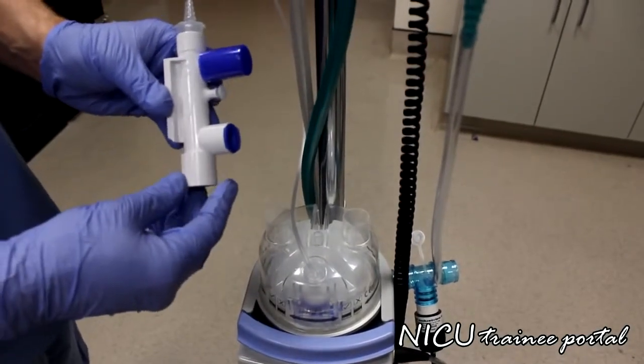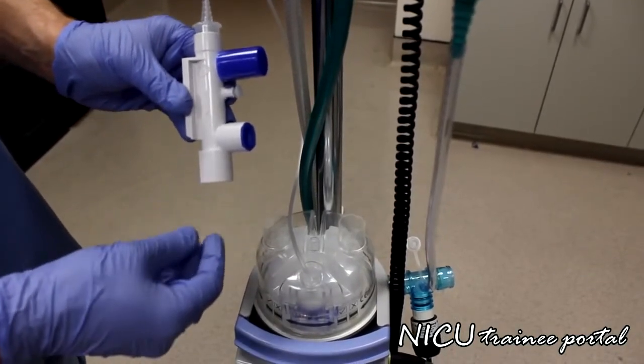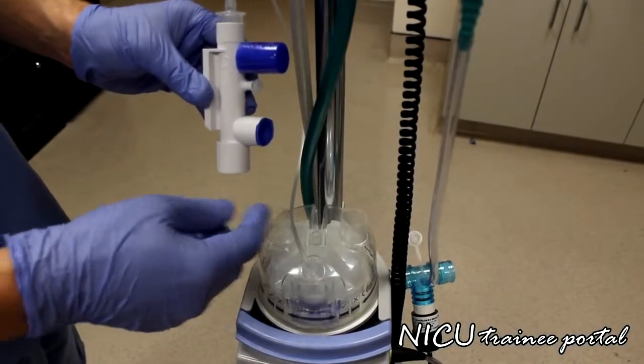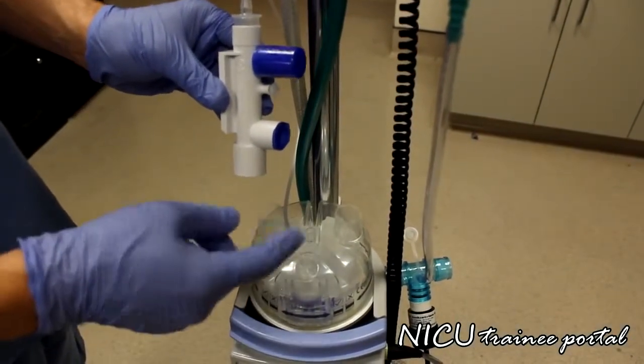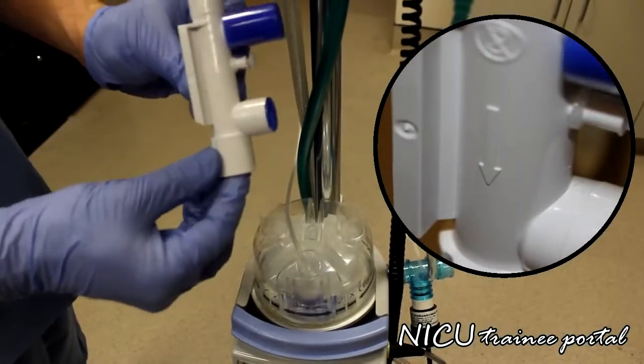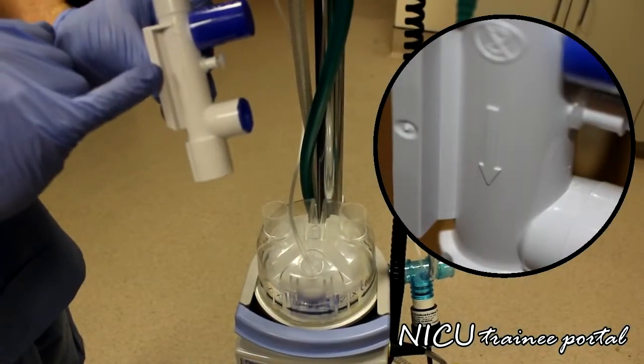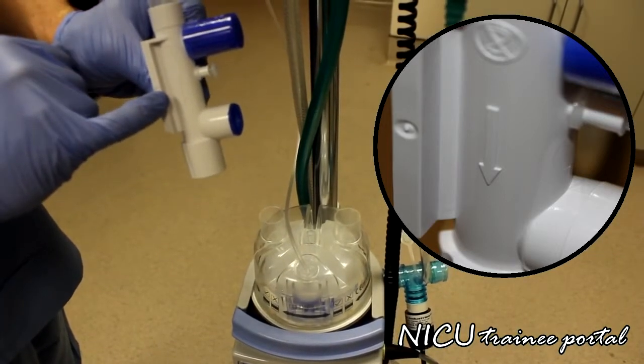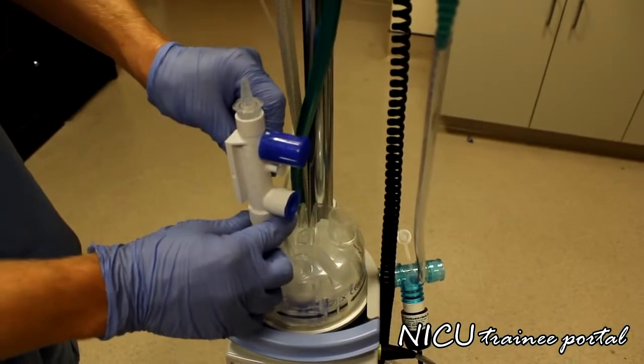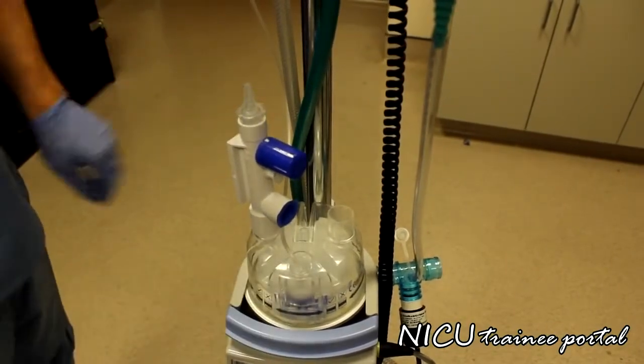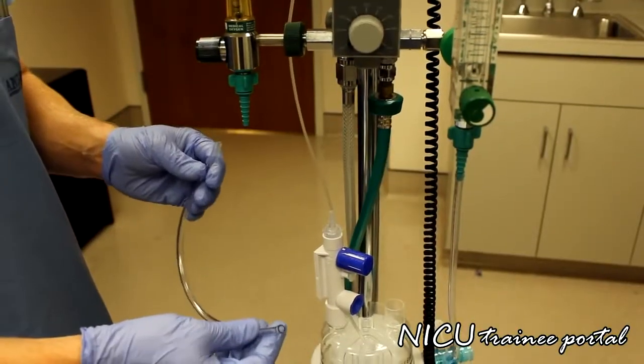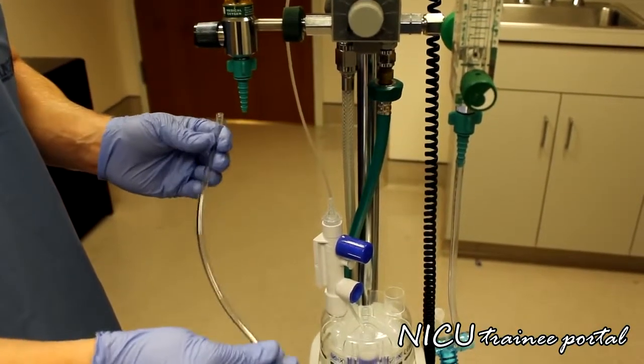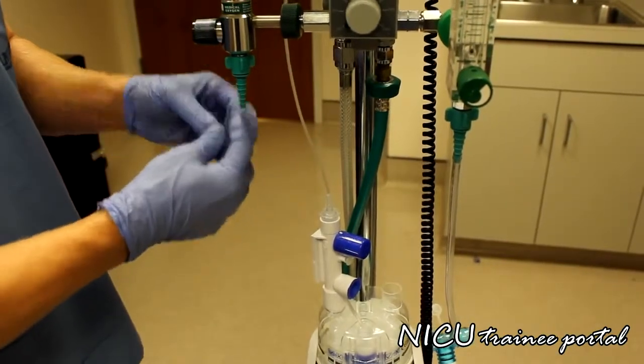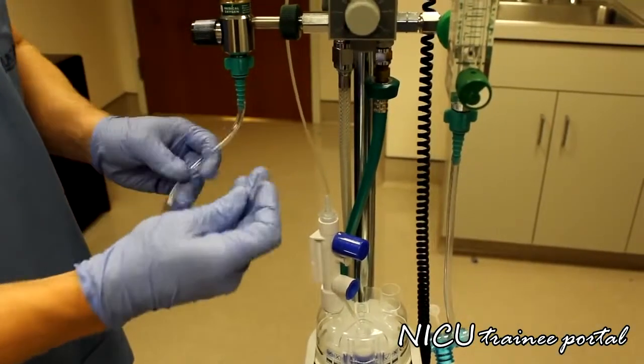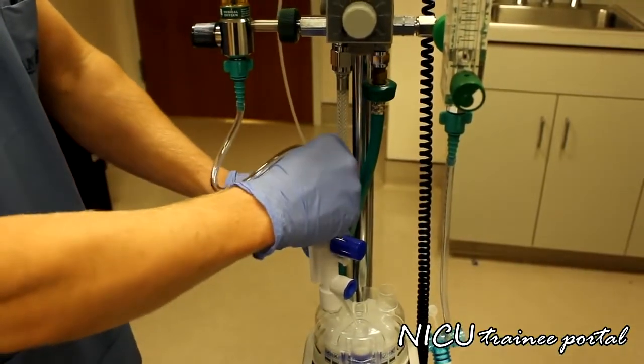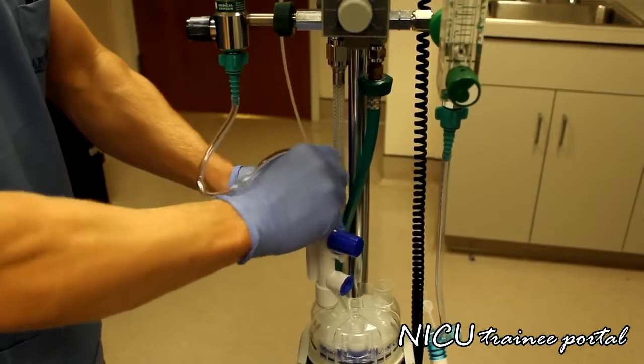Okay, so the next component we'll be connecting is the pressure relief device. This will be going on the water chamber. It does not matter which side it goes on. So if you connect it to either side, there is an arrow on the side of the pressure relief device which indicates the flow direction that you need to connect with. So this will be attaching to the water chamber just like that. Next piece is this piece of connective tubing. We are going to connect one end to our flow meter. The other end is going to go on top of the pressure relief device, like so.